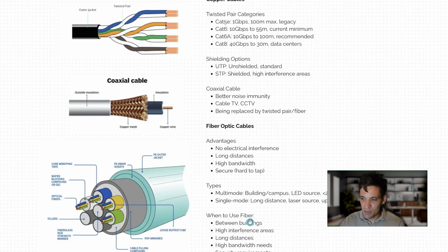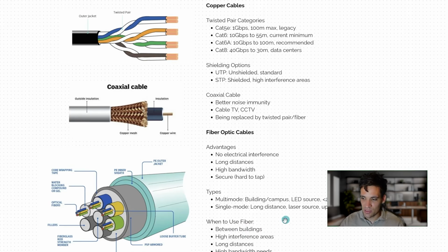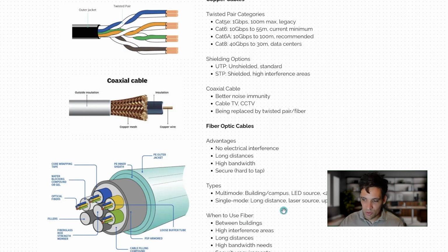You can have multimode fiber, which you run shorter distances, such as building campuses that use an LED source, or you can have single mode fiber, which can run very long distances up to 100 kilometers that use a laser source. So we'll use fiber generally. Fiber is much more expensive. It's expensive to terminate. It's more difficult. It takes more time. But you'll use fiber generally between buildings when you have to run cables more than 100 or 200 meters.